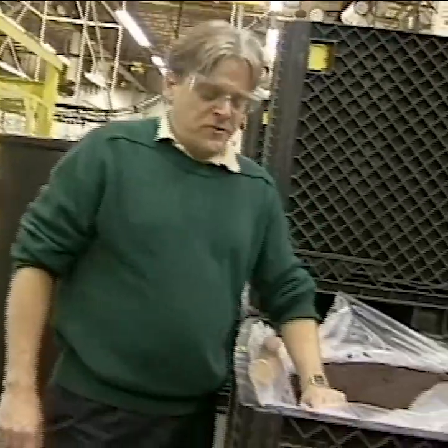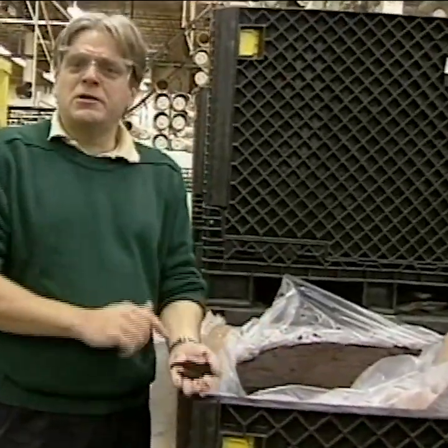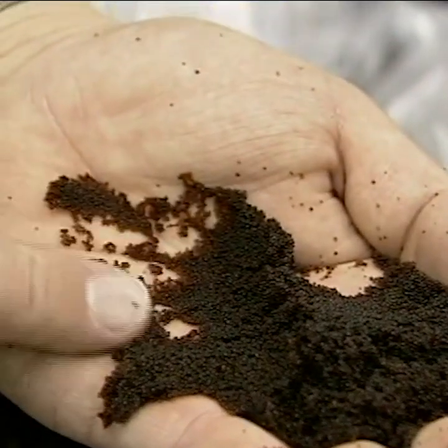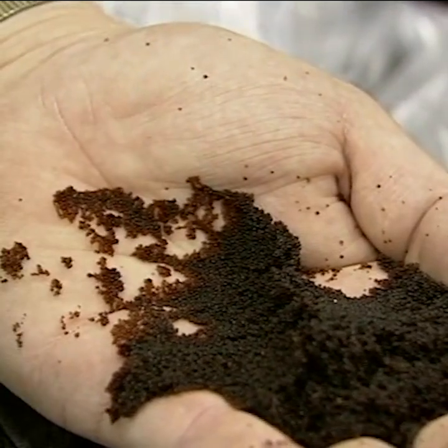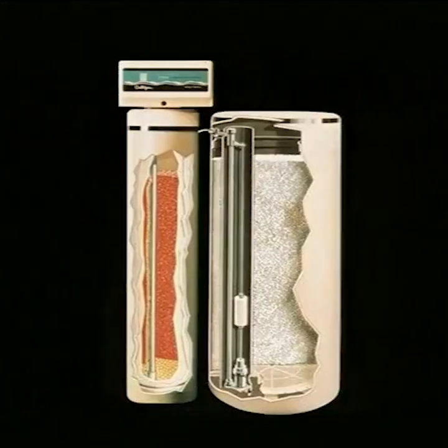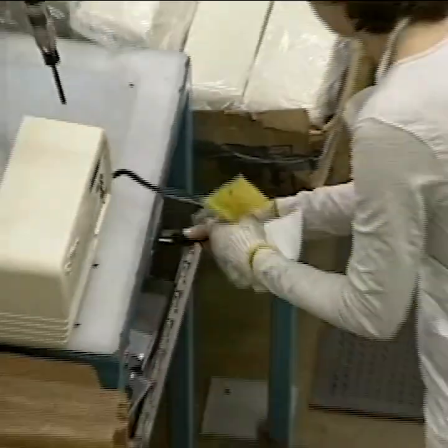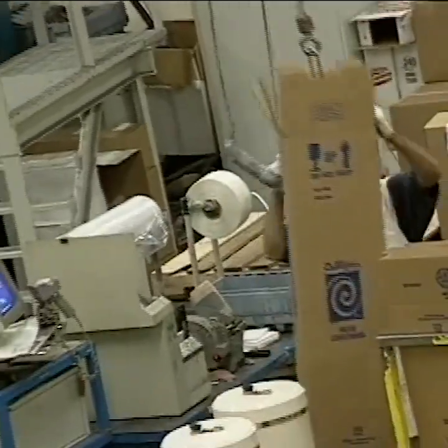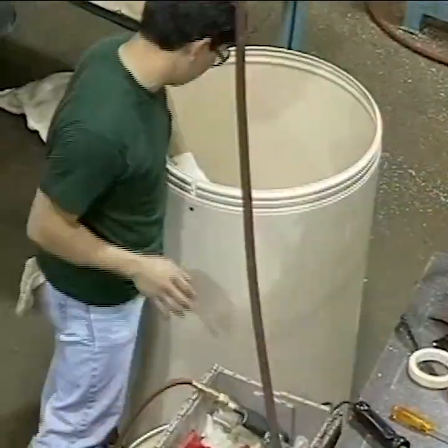A water softener uses a special media, commonly referred to as a resin. The resin is specifically formulated to have negative exchange sites. These negative exchange sites attract the positive cationic metals in the water. A water softener consists of 3 components: a control valve, which is the brains of the unit, a resin tank, which holds the media, which we saw previously, and a salt storage container.